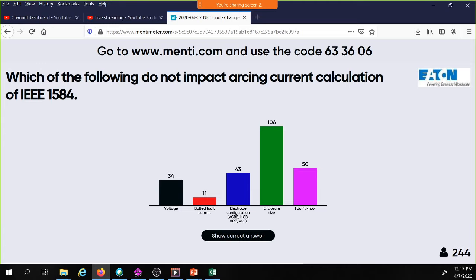Electrode configuration, VCB, VCBB, HCB, you probably don't know what that is, but you're going to learn that today. That definitely does impact the arcing current calculations. That tells you which way the electrodes are configured, and I will show you how it does. Enclosure size does not impact. So the 106 that are in that, pick the right answer, because the size of the enclosure really dictates how much energy is forced out.